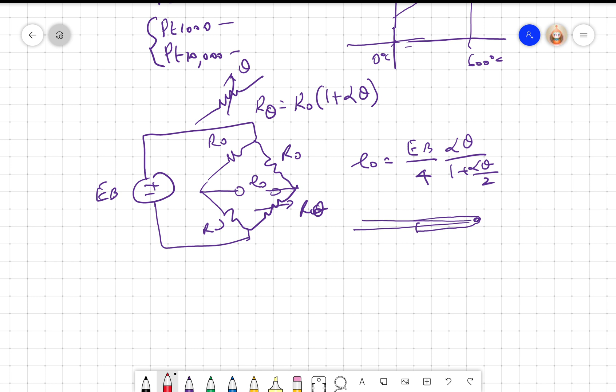So what happens is, if I put a large resistance, then here there would be wire resistance. So RW is the wire resistance. Please remember, whenever you want to measure temperature, the sensor must be sensing the temperature. For example, if you are going to sense the temperature of a heating element, you put the sensor on the heating element, but you can't put the electronics there because it will be too hot. So you'll have to put the electronics away, maybe half a meter, 1 meter, even 10-20 centimeters.